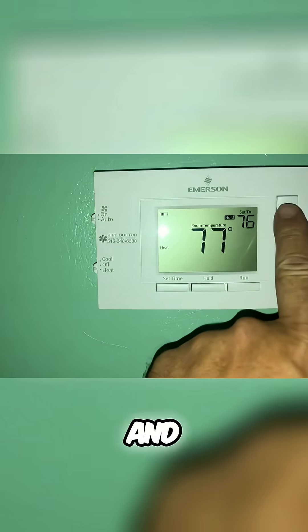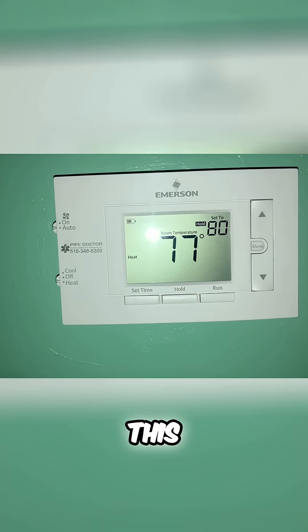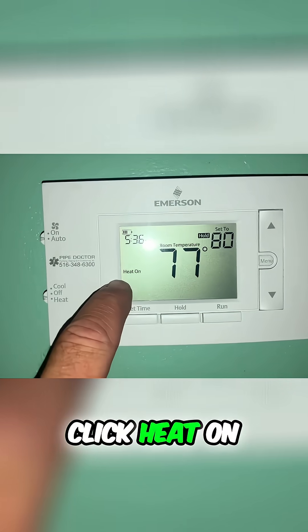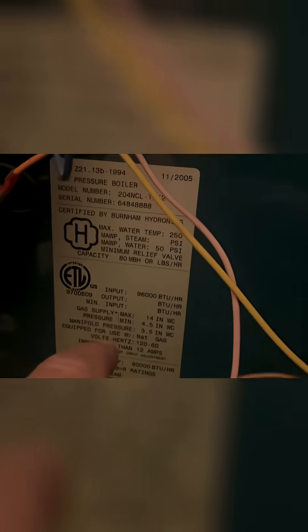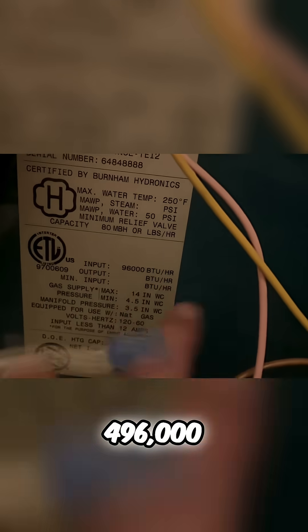On the one though it's 80 degrees up here. There's the click — heat on, there's another zone valve on, that's still on, and this one is off. That's hot and that one's cooler to the touch, circulating the second floor with 496,000 BTUs of input. Is that the other return?